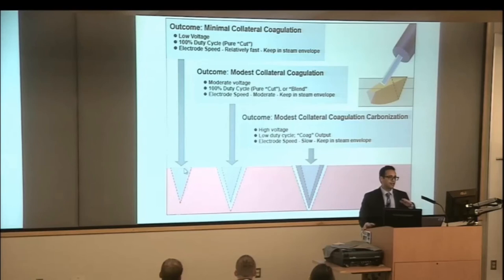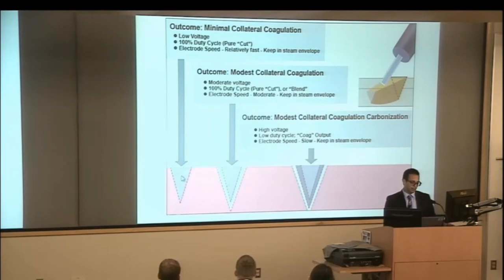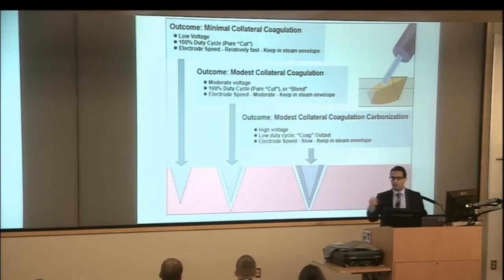This is a schematic cross-section of tissue. You apply your active electrode here using cut, so low voltage. The tissue it contacts rises above 100 degrees Celsius, so it vaporizes and you get that cutting effect. But because it's low voltage, the surrounding tissue doesn't really experience a rise in temperature, so it doesn't get desiccated.